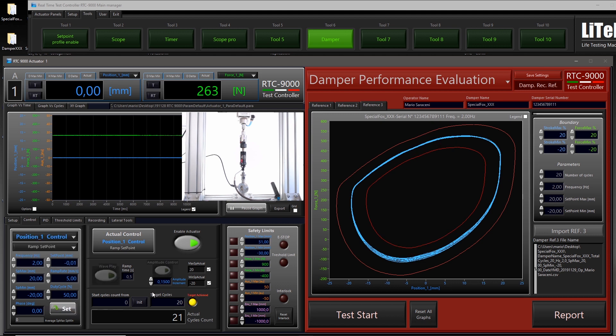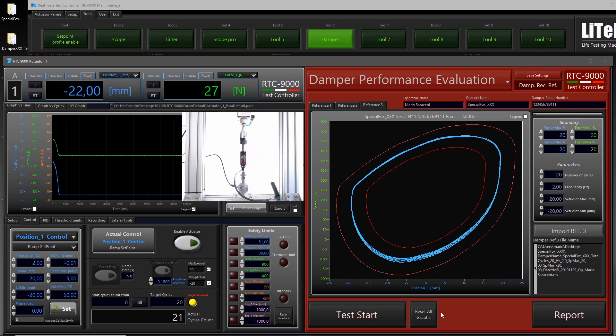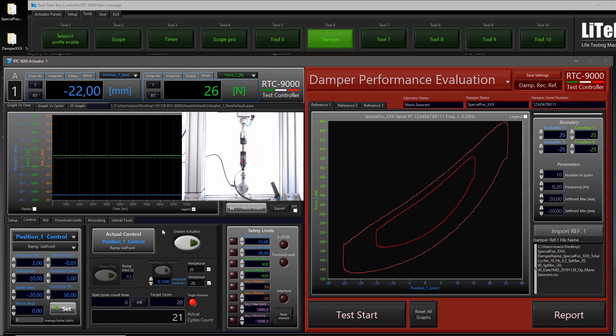Go to ramp set point and disable the actuator. You will see the damper fully extend in a safe way. You can then mount a new damper and perform a new comparison. Reset all graphs. If the new damper is the same type as the reference, you can keep the three reference files already loaded. Mount the new damper, do a short warm-up, and then start the test again.